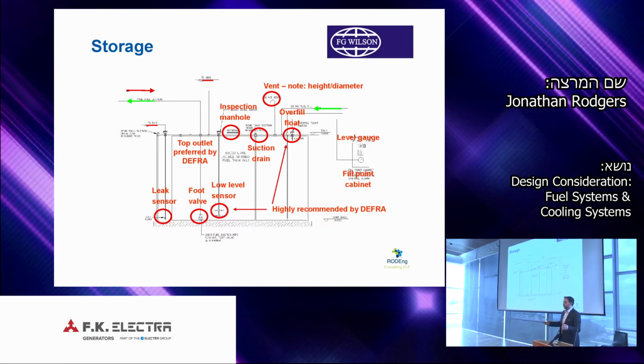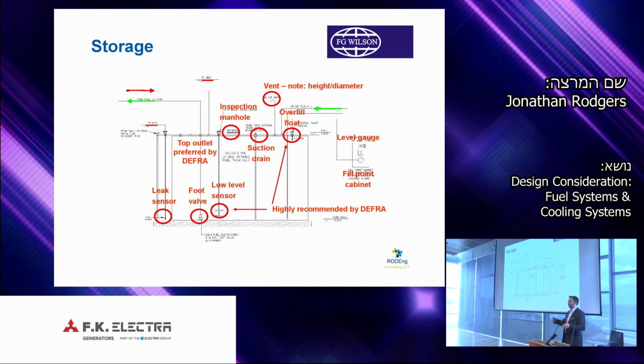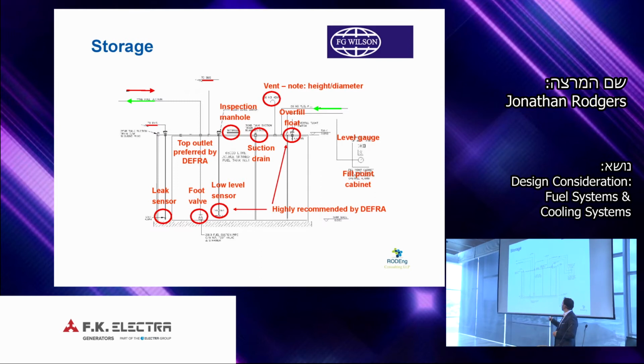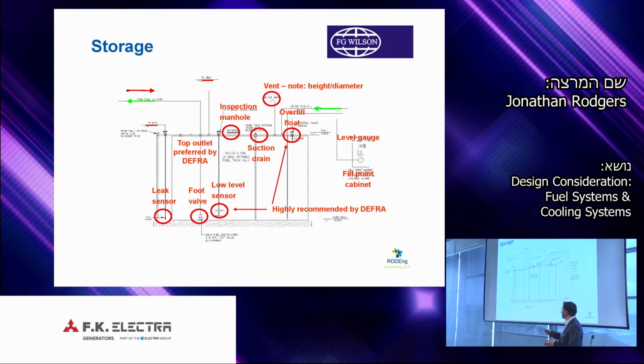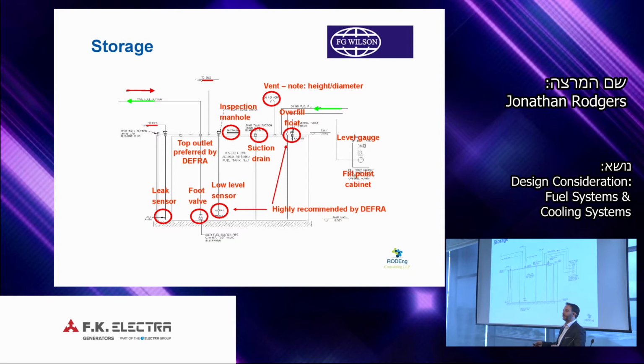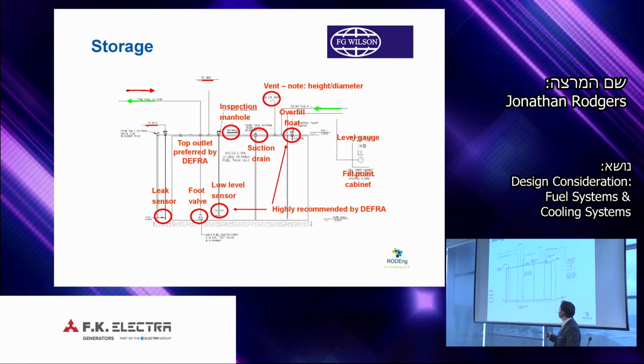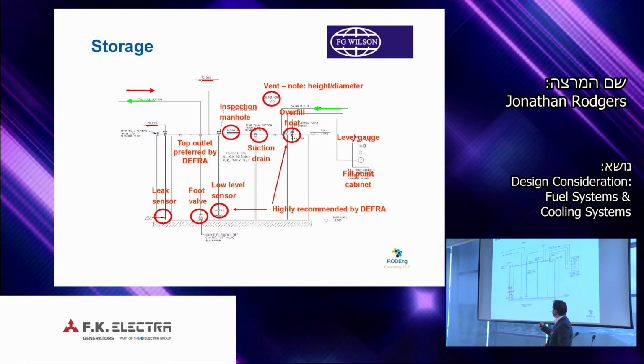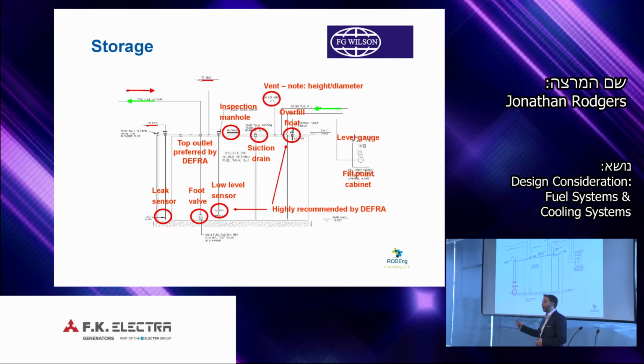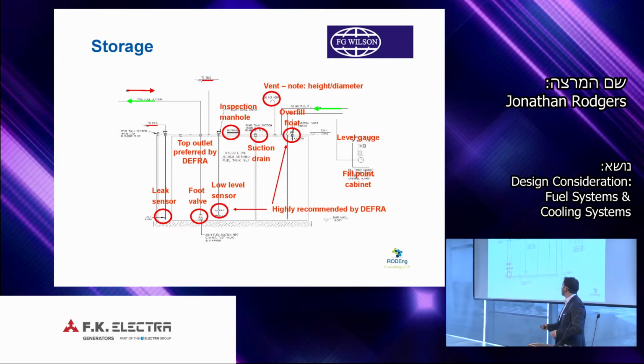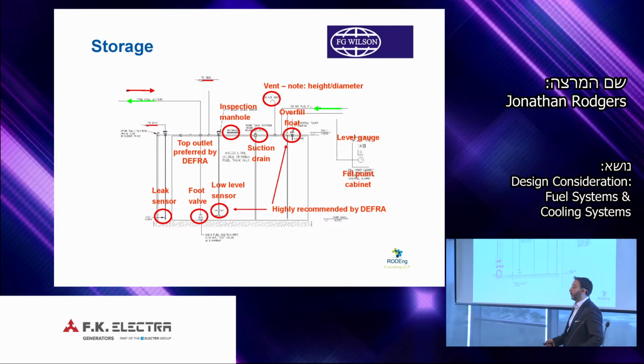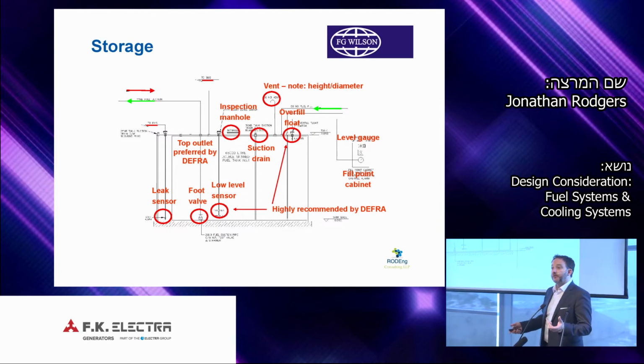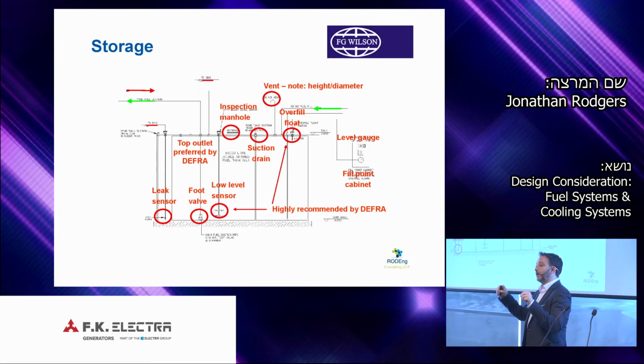I believe we'll have these slides available in PDF form for you. What we have here is a typical schematic and some of the key functions that we need to remember and why they're there. So this is the tank within an external bund, and within the bund we'll design to have leak detection, so if there's a leak into the bund, we know. We have a manhole for inspection, so we can check what is in the tank and check the integrity of the tank.